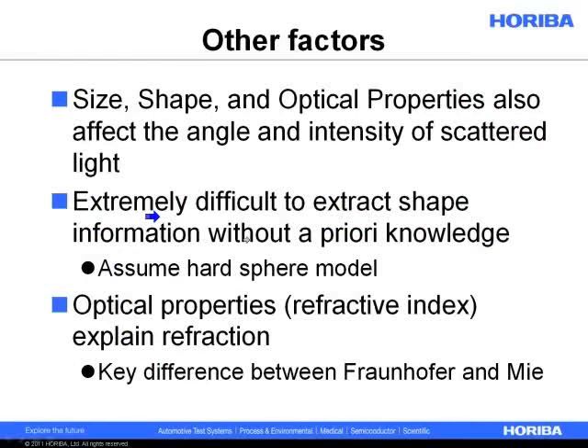Other factors that affect the light scattering pattern: in addition to size, shape and optical properties will affect the angle and intensity of scattered light. This is where we start needing to use the refractive index. In practice, it's extremely difficult to extract shape information without a priori knowledge. So what we do in order to get a solution is we assume that every particle is a hard, non-porous spherical particle. It simplifies the mathematics, we can solve it completely. It does add some error, but it's how we do the measurement.